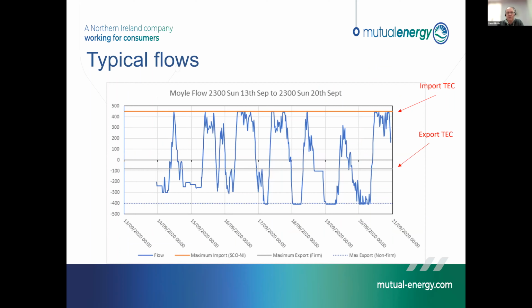Moyle's configuration, what you can see there in blue, is our original cables. I mentioned that we did have problems with those cables. They were a fairly novel design back in the day, a concentric design with the outer LV protected by polyethylene, and that polyethylene ended up demonstrating brittle characteristics. So the 2016 project addressed that by replacing the subsea sections with the new MRC cables, the metallic return conductor cables. Those meet the original cables at transition joints on our beaches.